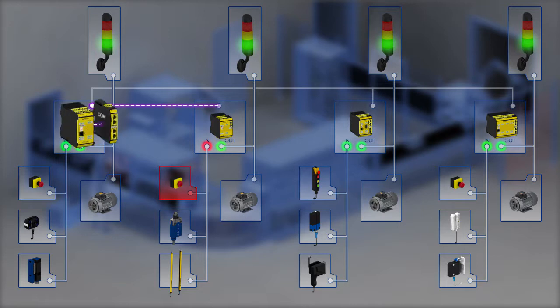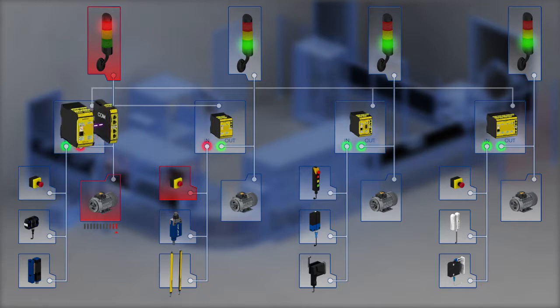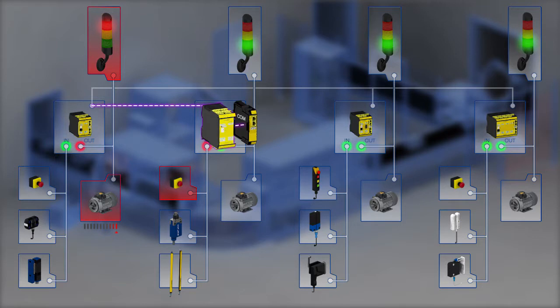The safety controller shuts down the drive in system component 1 via the safe outputs and stops the feeder process. The error is displayed via a status output signal. The detected fault 'emergency stop' is at the same time transferred to the internal universal communication module. The communication module sends the command 'shutdown outputs' to the remote I/O module so that the motor is shut down.